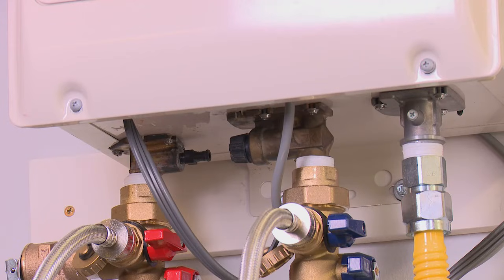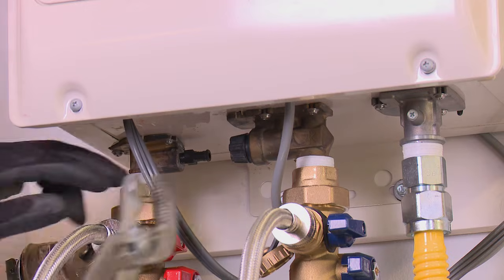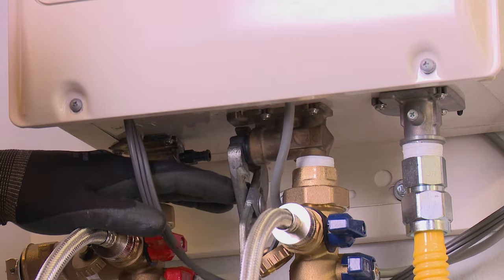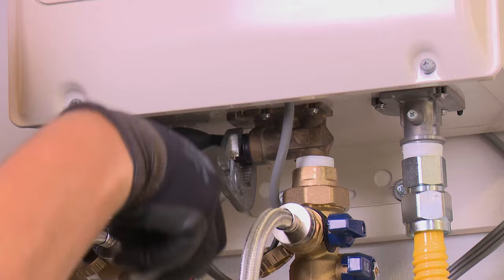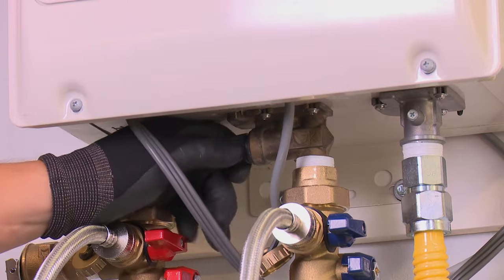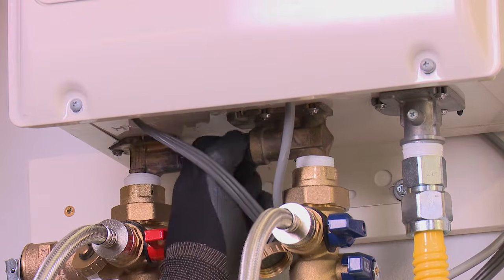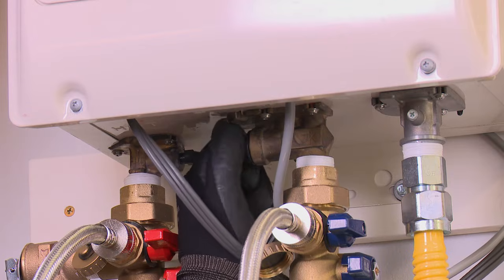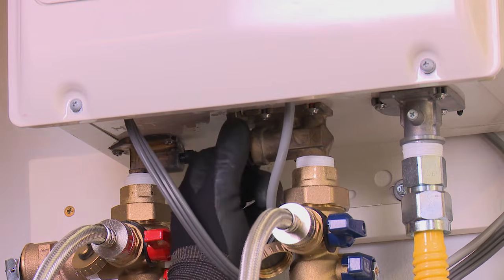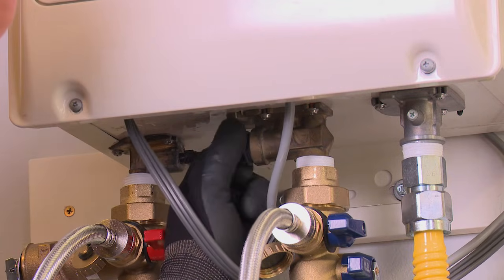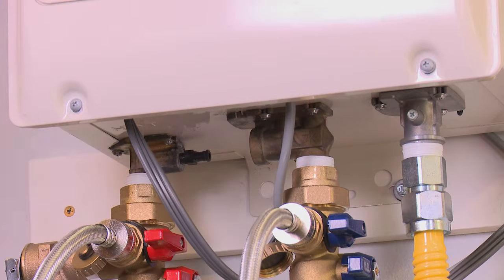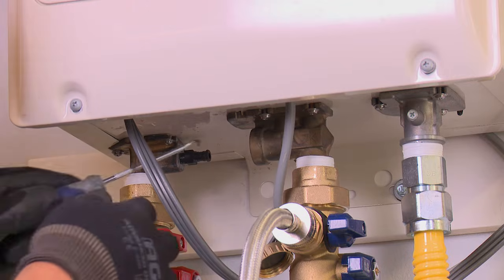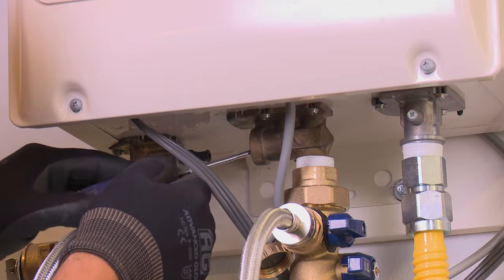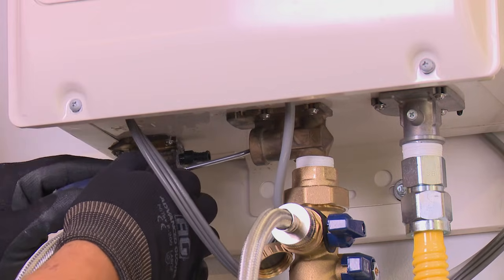Now we're going to remove the inlet filter and clean it. First step is removing the plastic plug holding the filter in place. Gently put your channel locks on the filter plug and loosen. If the filter doesn't come out with the plug, you'll need your removal tool to gently hook the filter and remove.